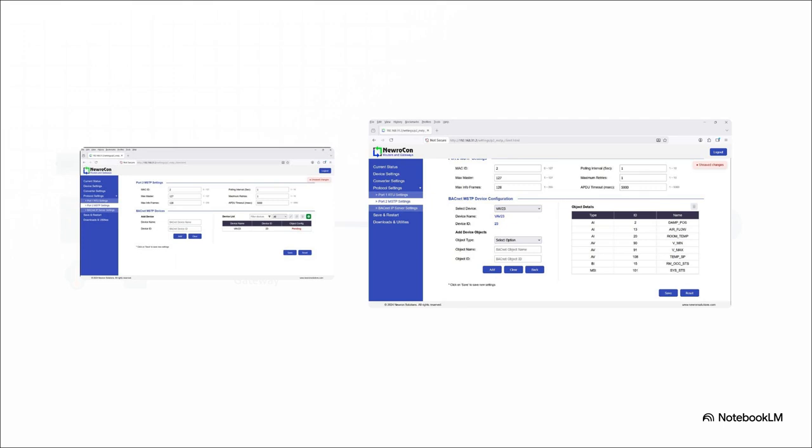If you compare that empty pending screen we had a second ago to the fully populated object list, it's night and day. We just repeat those exact same object creation steps for airflow, room temp, v_min, v_max. You get the idea. By relying entirely on the datasheet, we're building a comprehensive profile for the VAV box. It's just a highly logical, step-by-step translation from paper straight into the software.